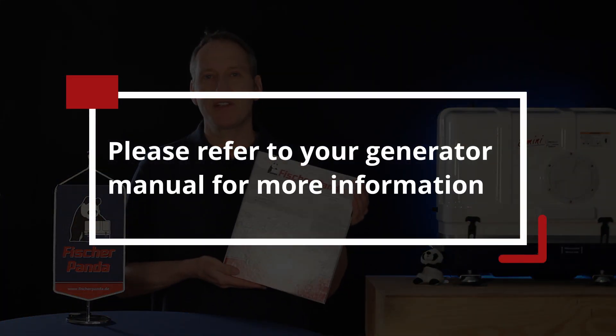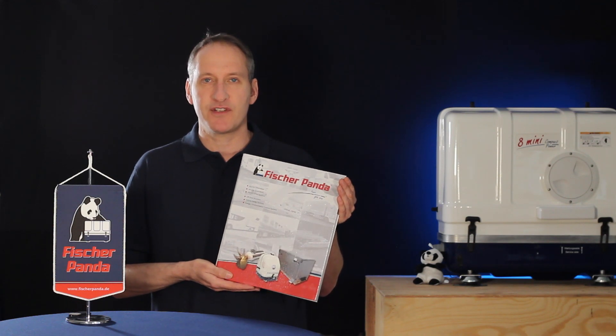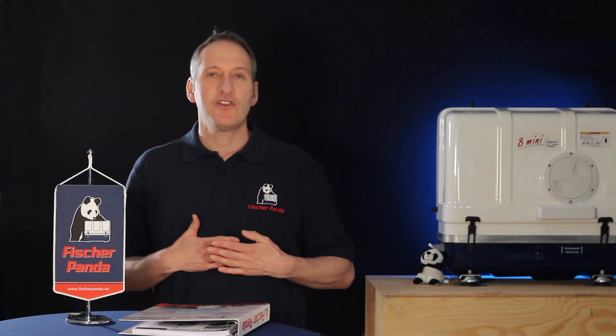Please consult your Fischer Panda generator manual for more information about operating your generators in parallel. You cannot connect standard Fischer Panda I-Series generators in parallel without parallel-capable inverters. To tell if your I-Series generator is capable of being operated in parallel, look on the back of the inverter housing — there is a socket for a synchronization cable, which is used to connect the inverters together in a parallel setup.